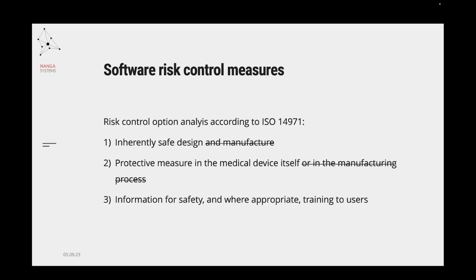Number one, inherently safe design. Number two, protective measures in the medical device itself. And number three, information for safety and where appropriate training to users. Good practice is starting with defining a safe state where the software or the medical device cannot cause harm or can cause very little harm.